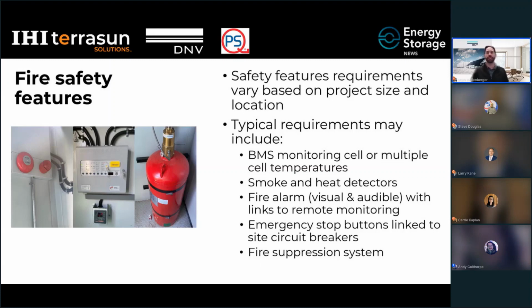Now, traditional fire detection equipment such as smoke detectors and heat detectors are often used, but in cases where battery cells have little separation between venting and thermal runaway temperatures, these external detection methods might not be effective in detecting anomalies until it's too late to stop thermal runaway. So that's why when we're looking at the cell level data, the larger the separation between the venting temperature and the thermal runaway temperature typically means that the system has more leeway to act to prevent a catastrophic event. So the battery cell resistance to thermal runaway, as determined in the module level UL9540A tests, becomes of high importance too. Because if we have thermal runaway in a cell that's able to propagate, we can have a cascading effect where multiple cells within the unit can off-gas and generate large volumes of flammable gases.